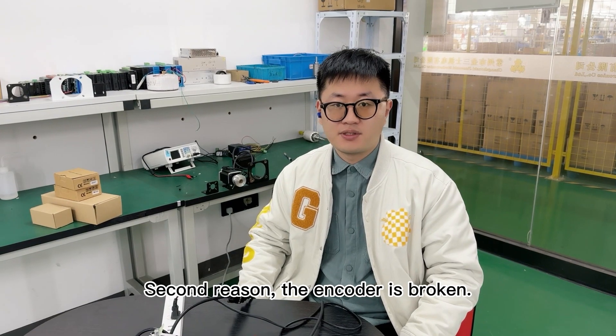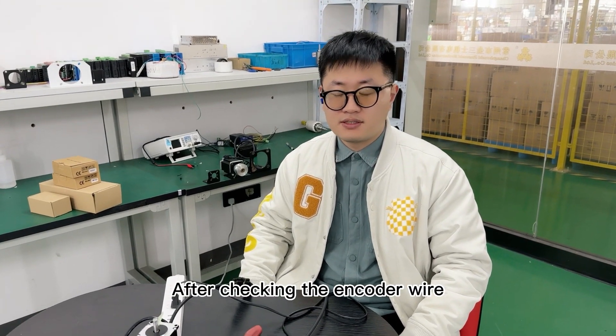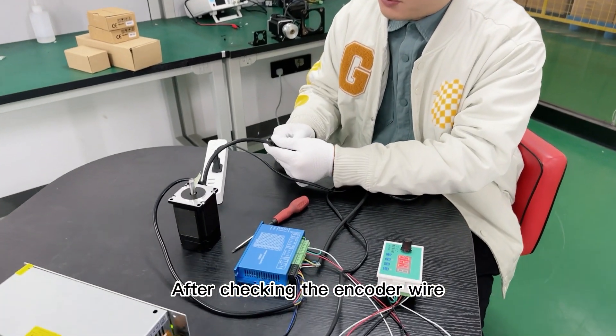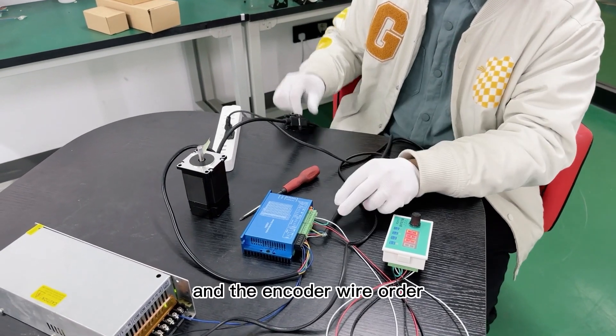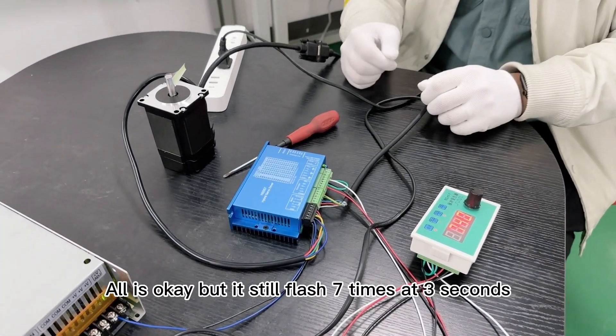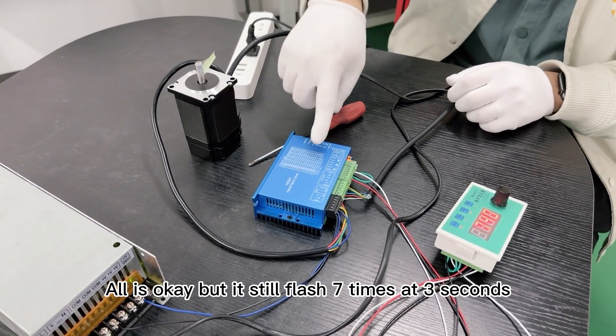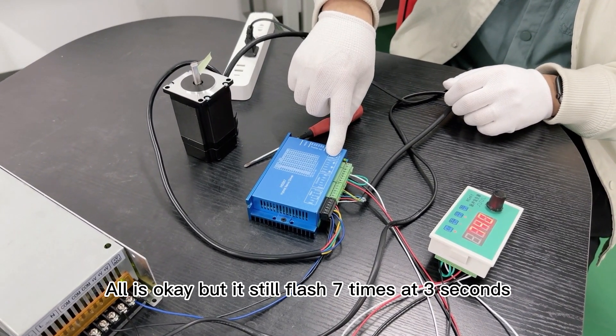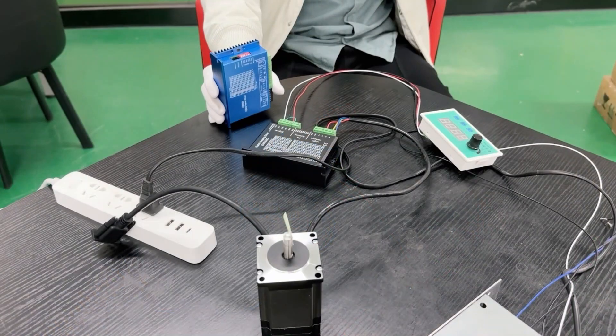Second reason: the encoder is broken. After checking the encoder wire and the encoder wire order, all is okay, but it still flashes seven times within three seconds.